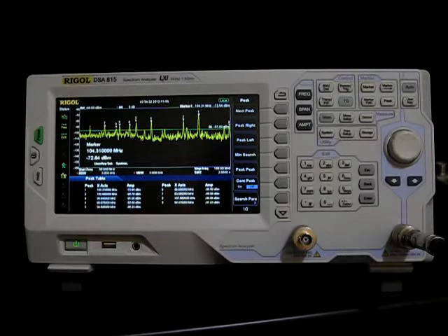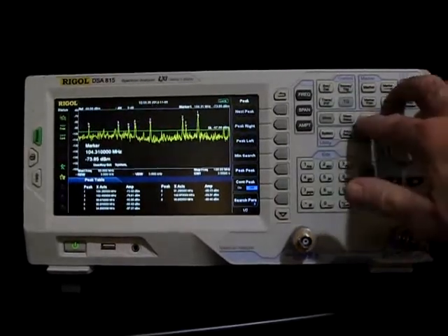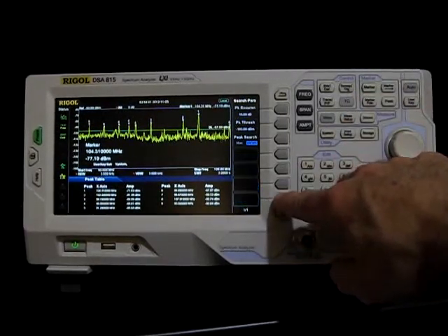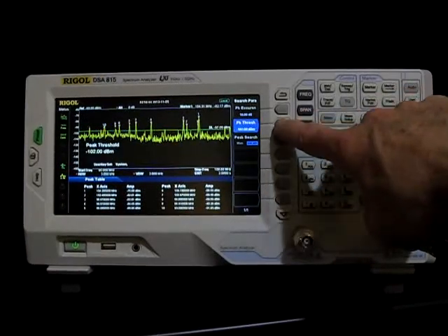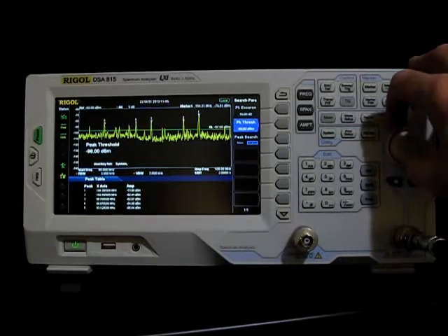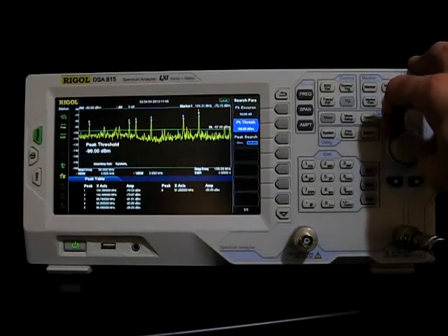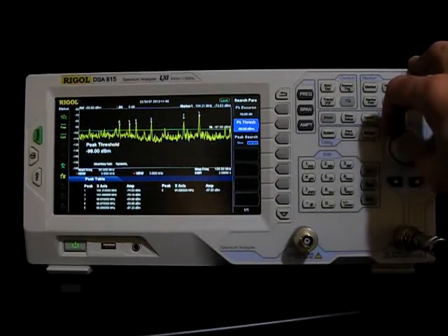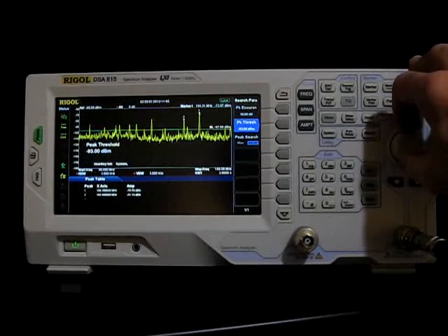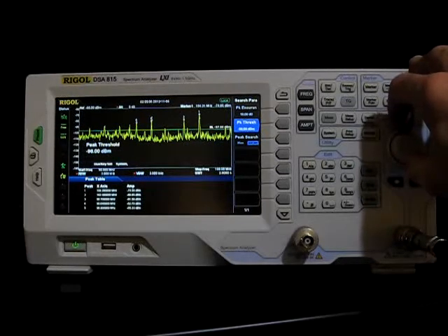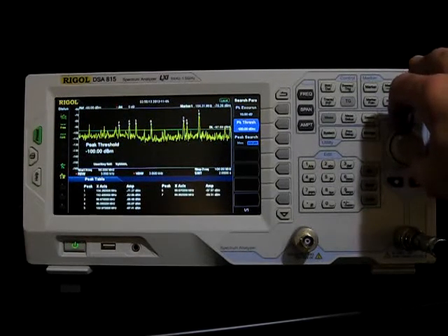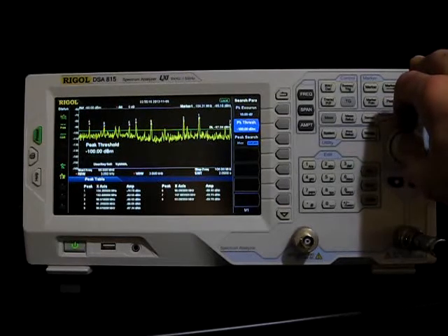You could set a threshold. I can show you that if I can find it again. Search parameters, I believe. And then right here, peak threshold — you press that one. You can actually use the encoder knob and adjust the point at which it starts detecting. I'm cranking it up so that it takes a stronger signal now to make an entry into the peak table. As I go up, they start to diminish because the signals aren't that strong. And as I lower it and go to a higher negative dBm number, more of the signals on the trace qualify for that table, and they get added accordingly.